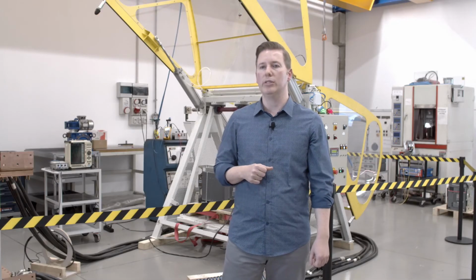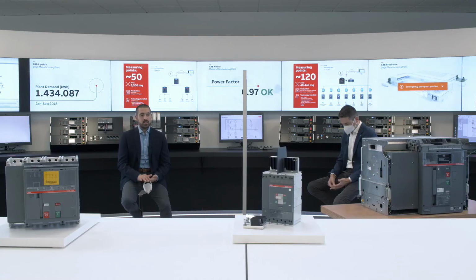Okay, just last question. What about the time constant during the interruption phase? Yes, time constant is an important value for the circuit breaker. It is given by the international standard and represents the duration in milliseconds of the short circuit during the test in laboratory. It is possible that the same circuit breaker has different breaking capacity according to different time constant. For example, on our catalog, it is possible to find for the T4 MCCB two different breaking capacity, 25 kiloamps with a time constant of 1 millisecond and 10 kiloamps with a time constant of 5 milliseconds.